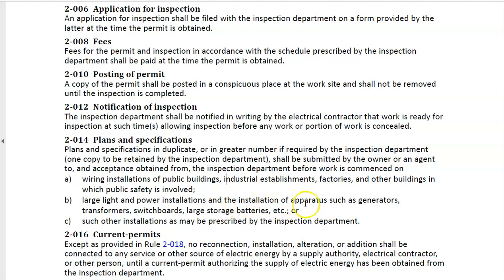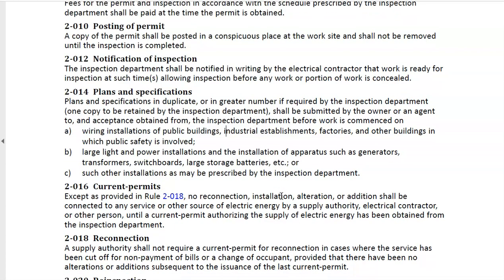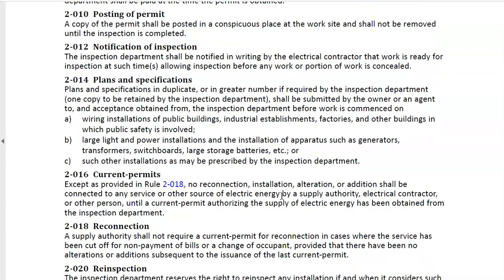Plans are also required for large light and power installations and apparatus such as generators, transformers, switchboards, etc., or any other such installations as may be prescribed by the inspection department. This is so they have an idea of what they're coming into and can do pre-review before arriving on site. The current permit is the last section of a job, where you have finished the installation and are now asking for connection — for power to be applied to it.